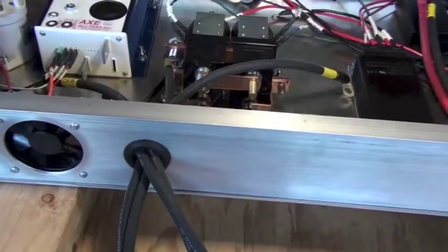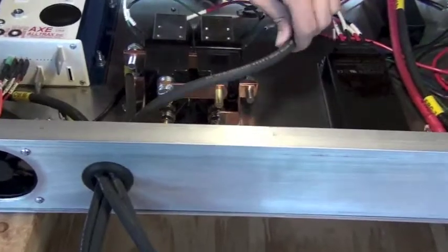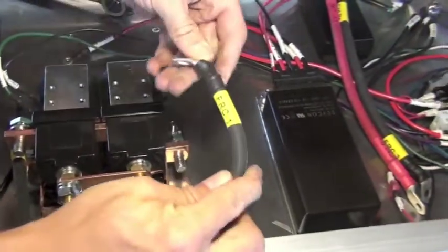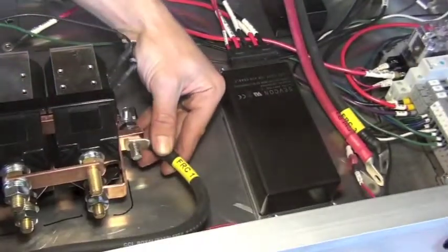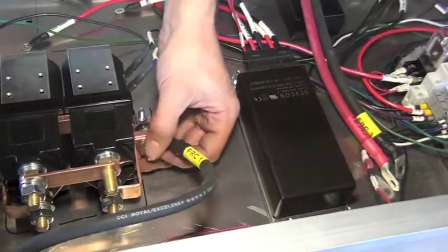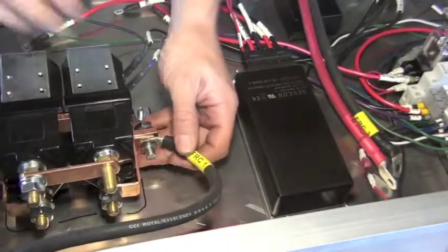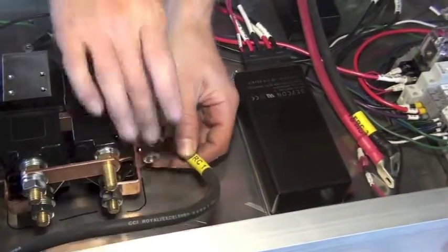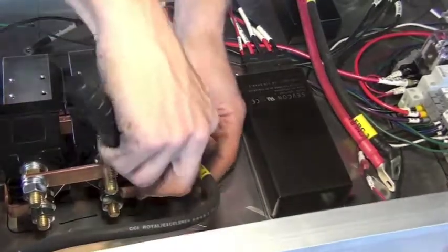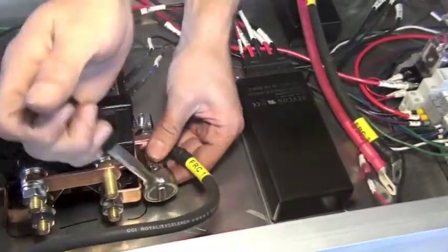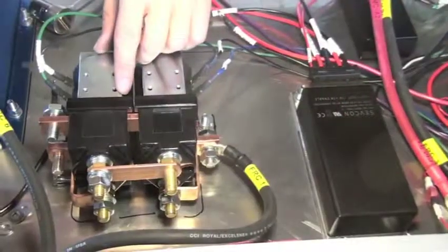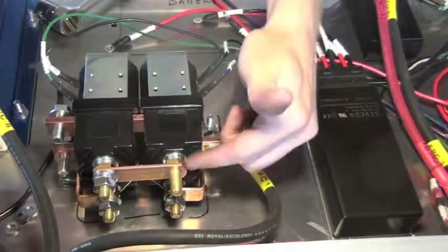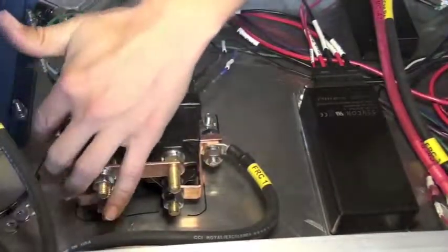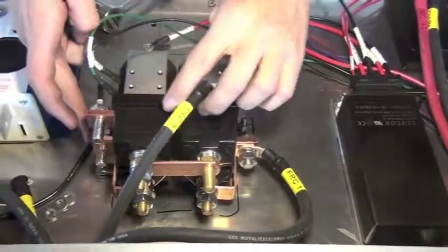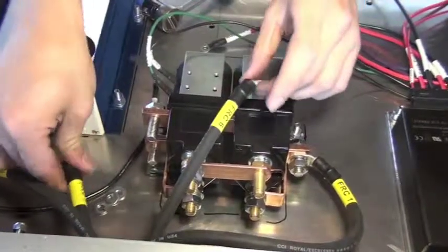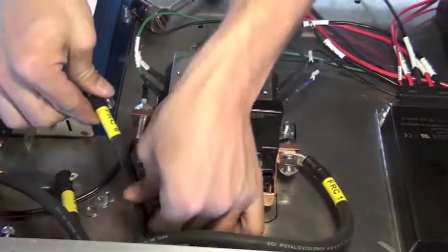So we'll start with forward and reverse contactor cable number 1. You can see it's clearly labeled, and it goes on to the number 1 position with a washer, lock washer, and then nut, and then we'll tighten it down. So if we count our way across these terminal connections, like the way they're labeled in the image, we can see we have 1, 2, 3, 4, 5, 6, and then 7. And since 6 is on the bottom, we'll install that one first. It'll be easier to access that way.